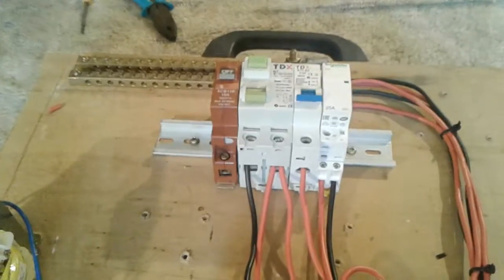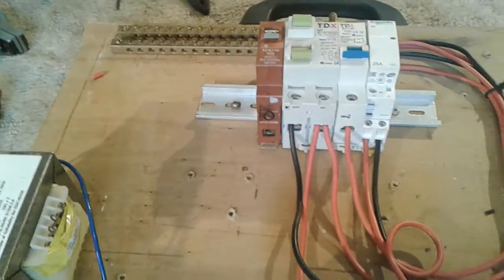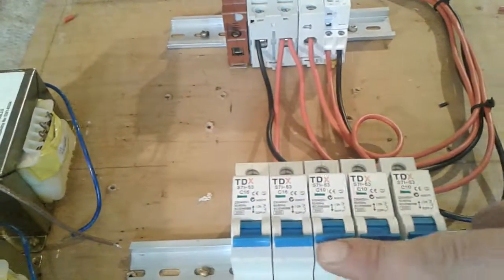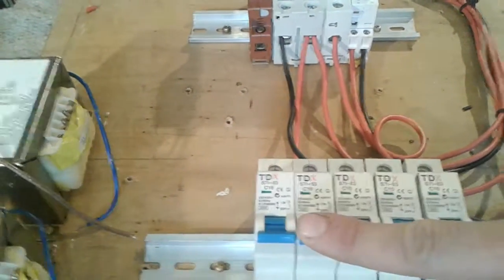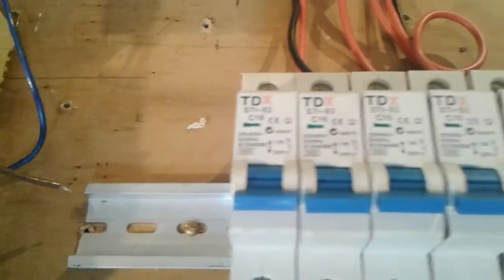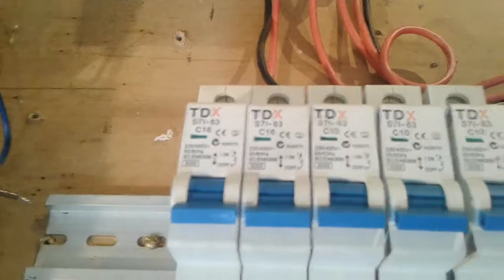So what I'll do to test which circuit has the RCD trip fault: I'll reset the RCD, turn on the main, and power each and every circuit to see which one it is. For example, if it's the 16 amp one — which would be the auxiliary power point just here.